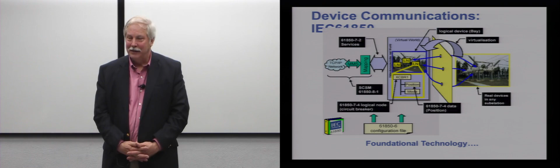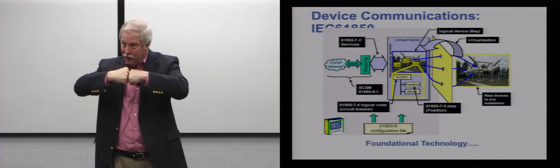If you have two gears getting ready to mesh on a car, and the two gears aren't aligned when you release the clutch, what happens? It's like auto-reclosing, but a specific kind. If the angle between the two ends of the line is very large when you close the line, you get a lot of power flow through that line instantly. That's not good to do - it really puts a lot of stress on the contacts of the circuit breaker.